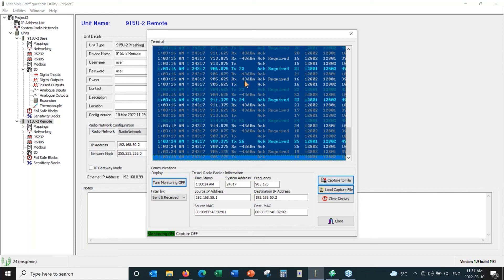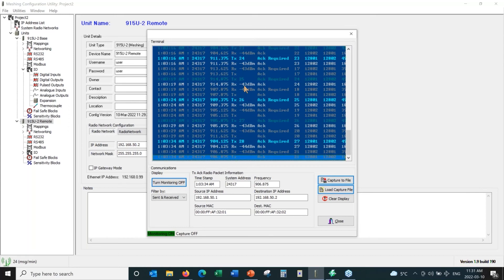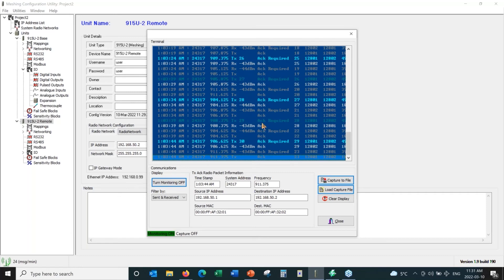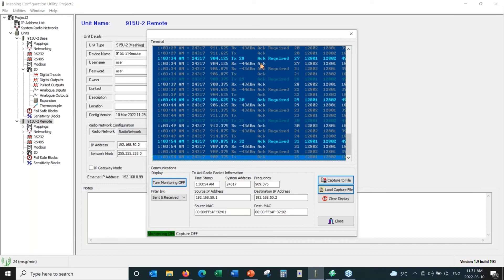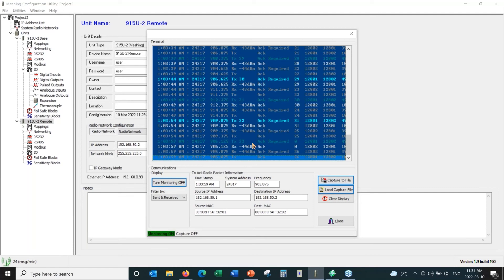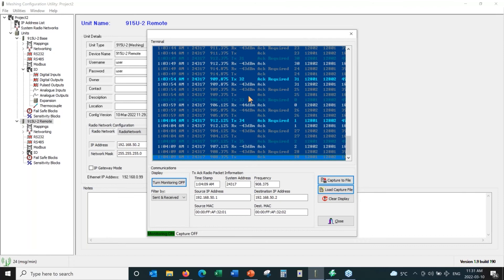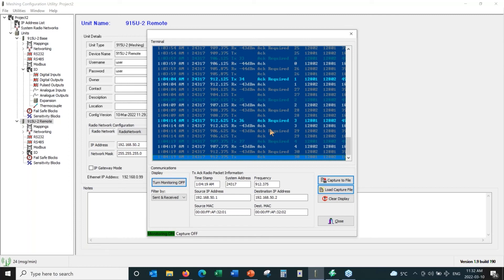We can see the received signal strength — it is negative 43. These radios are side by side, and I do have attenuators connected in series with the antenna. This shows what type of messages are going back and forth — we can see a transmit carrying those 4-to-20 values, followed by the acknowledgement coming back. These radios are successfully communicating. The RSSI is pretty much rock steady. I have the attenuators because otherwise the radios would saturate due to such strong signal strength. This gives a rough idea of what's going on to confirm the radios are communicating properly.